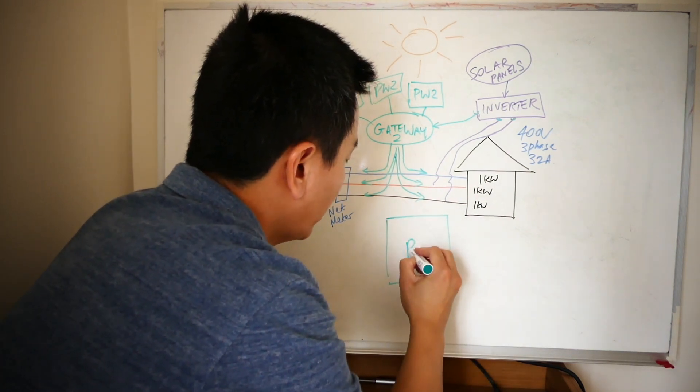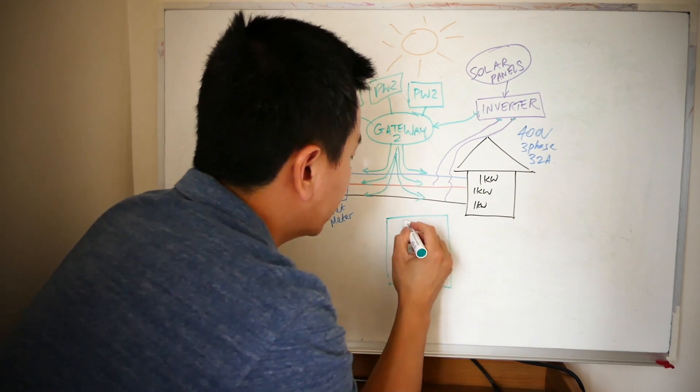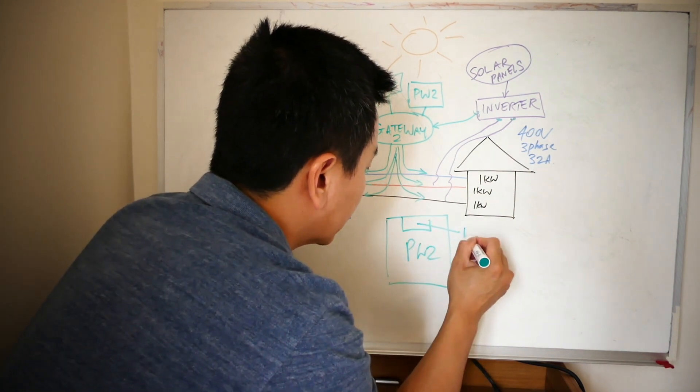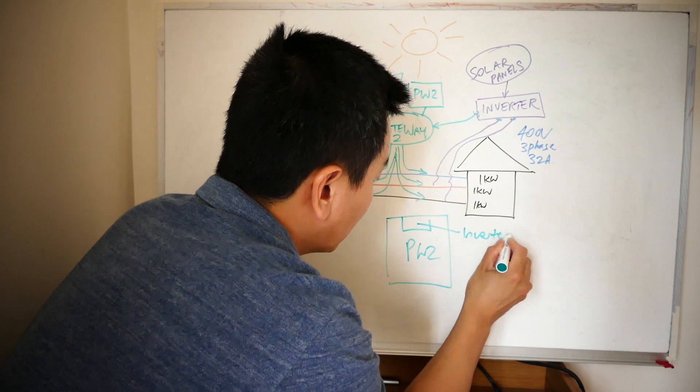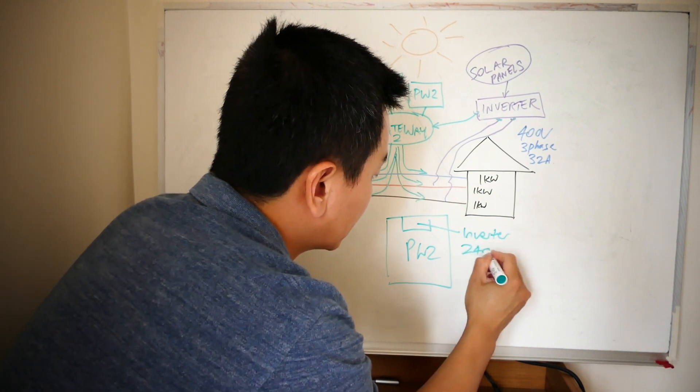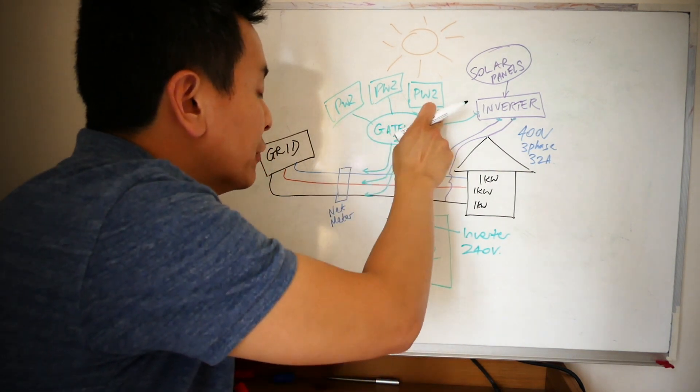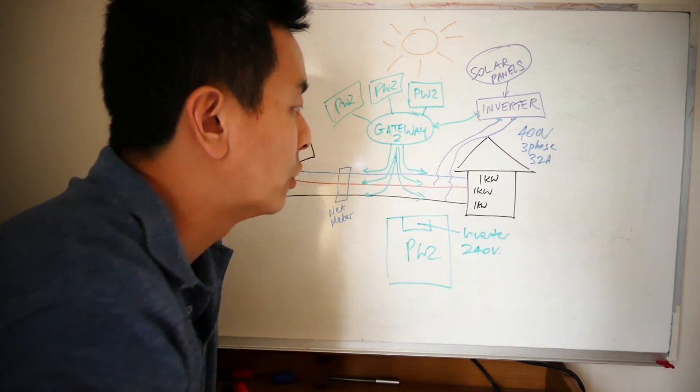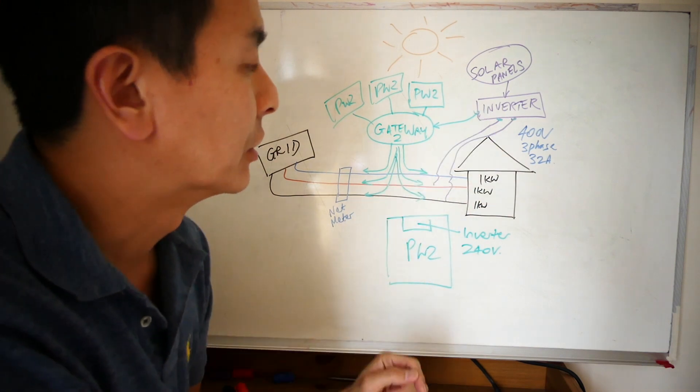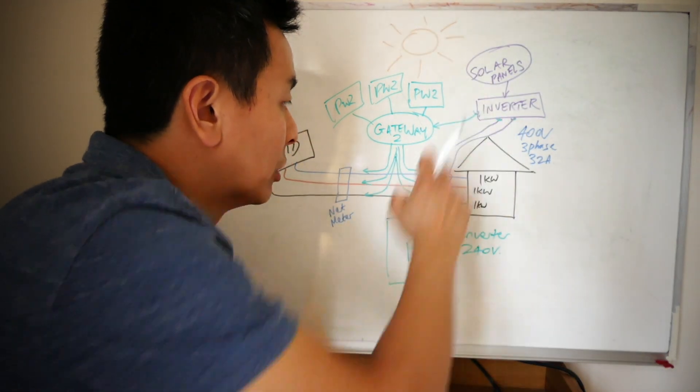Well, AC coupled means that there is a built-in inverter in there that will only allow 240 volts. So as you can see, even if it's 240 volts on each phase, it cannot supply a 400 volt supply to the solar inverter for the solar panels.